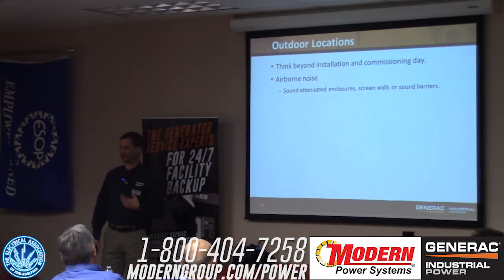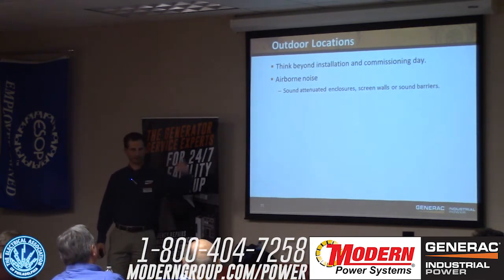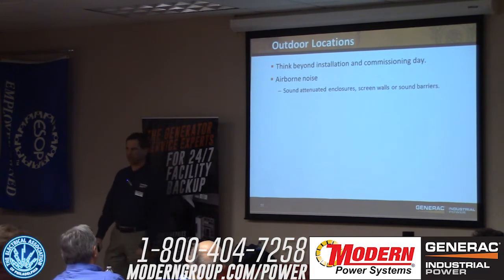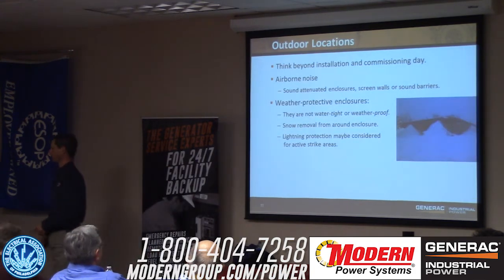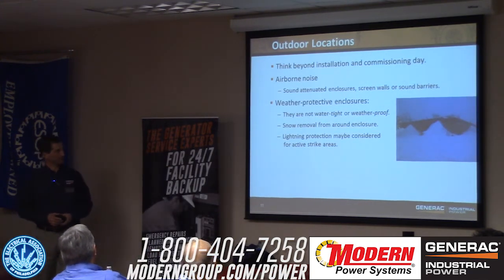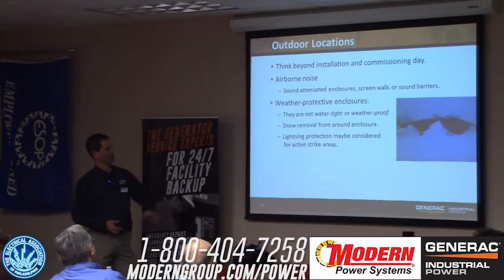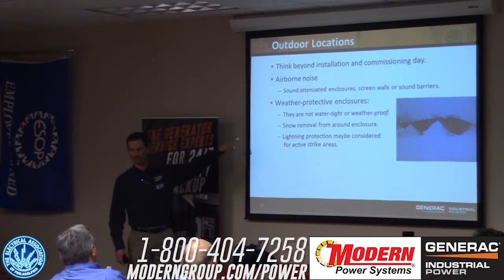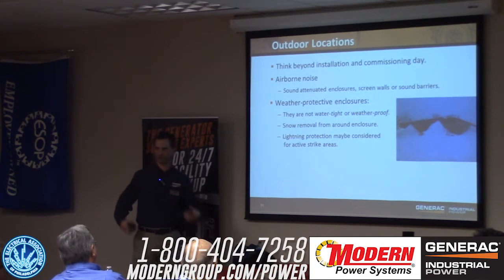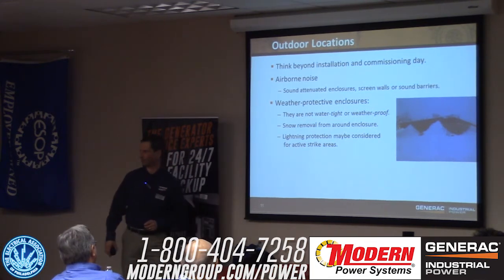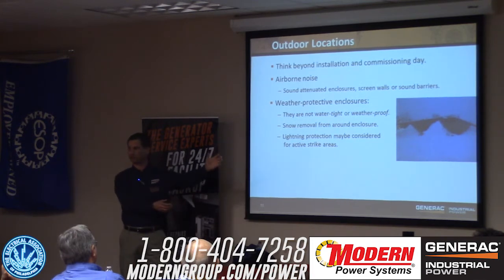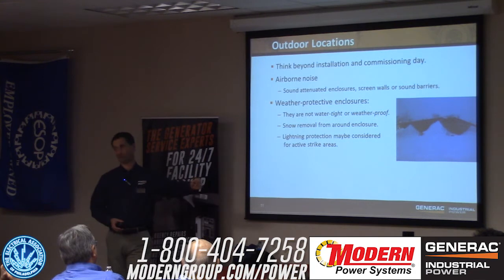You can do screen walls, sound barriers, sometimes shrubs kind of buy you that little extra margin that you need. Weather protective enclosures, they are not submersible, watertight. You are going to pull some moisture into them. When this machine starts, I'm moving 10, 20, 30,000 CFM through the enclosure. If it's raining out, some of the water's coming with it, okay?